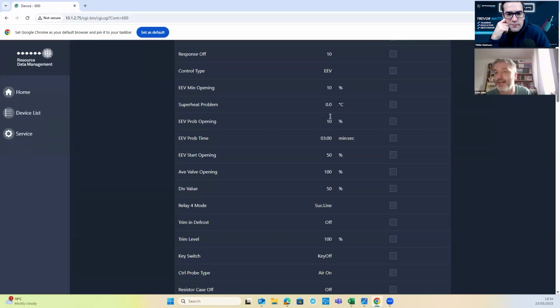Yeah, and depending on how you set that, it's either going to shut the valve or it's going to keep the valve at a low level. The problem when you're only controlling on probes, if you're not using a transducer to get your inlet temperature, your evaporating temperature, if you shut the valve completely, you may, let's say the coil's absolutely clear and you just had a rack issue, when you start it up, it may struggle to get away because you've not got any temperature sensed at the inlet. So you can set it to keep a little bit of refrigerant coming through on the basis that 10% shouldn't flood the coil. But if it's a fully iced up coil, it may well flood the coil at 10%. So if you've got a transducer, there's nothing to stop you setting the probe opening to 0.